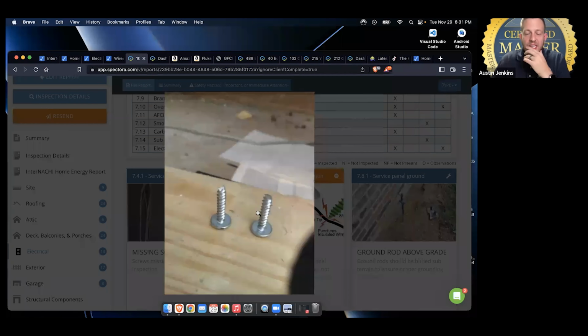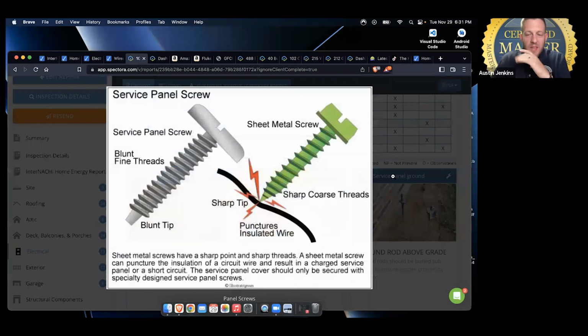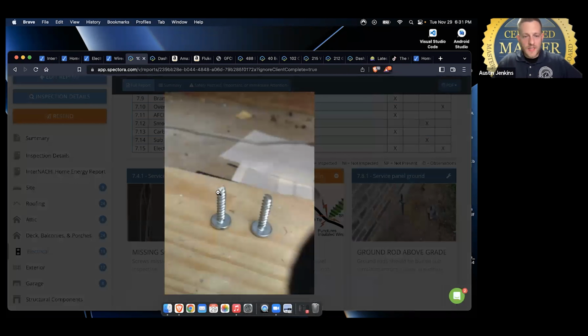This one was one of my favorites. One thing you want to look out for when looking at an electrical panel is to make sure the screws holding the dead front cover on do not have sharp edges -- they need to be blunt tipped. Just because you cut the tip off doesn't mean it won't still have sharp edges. Usually, if I'm doing electrical work in a house and run across screws that are sharp pointed, I'll take an angle grinder or a sander and just put a blunt tip on them.